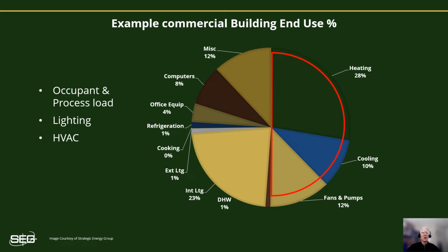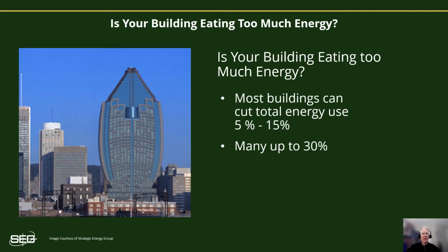Now let's look at what loads facilities managers and building operators can more readily influence. It's typically 3/4 of the whole pie here that you have the ability to impact, and up to 1/2 of it is just HVAC. So you can see why we like to recommend focusing attention on HVAC and controls when looking for energy savings opportunities. We find that most buildings are capable of using less energy with little to no impact on the occupants or productivity. We often see 5 to 15% savings within the first year or two of using the 4 common opportunities.